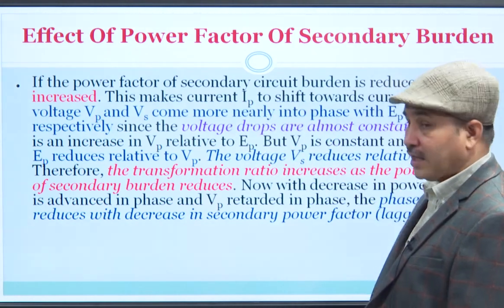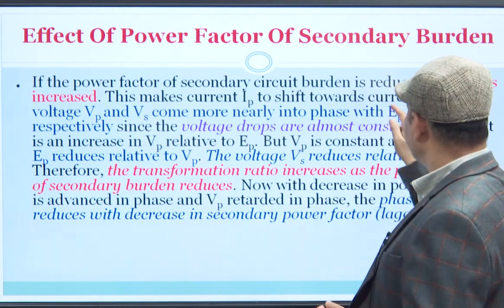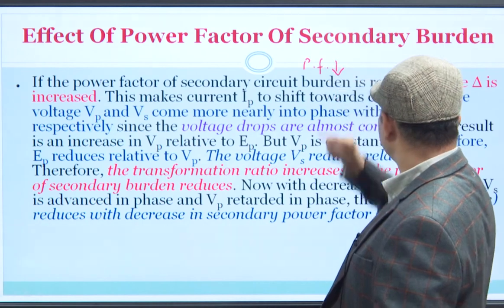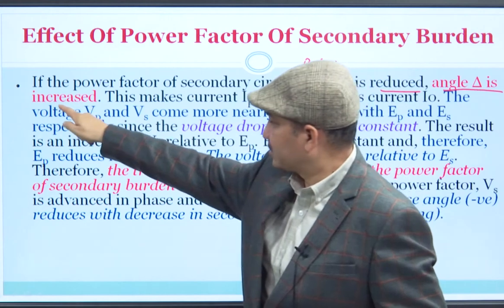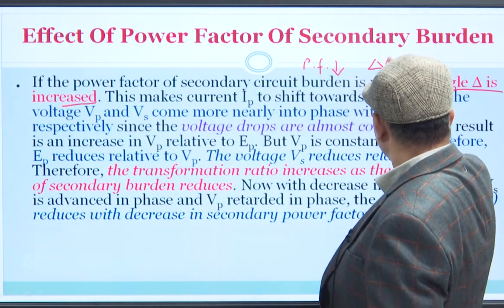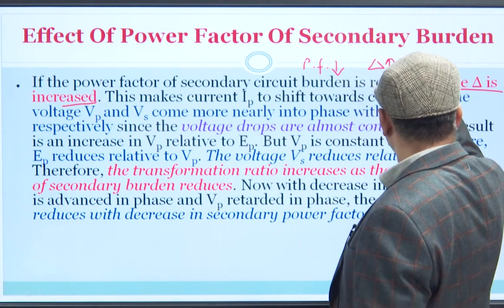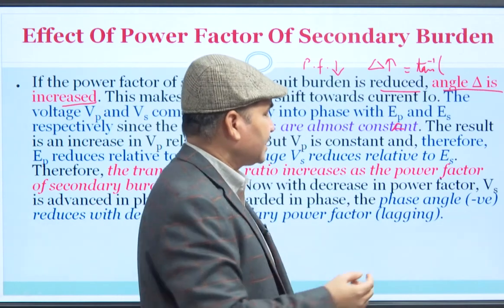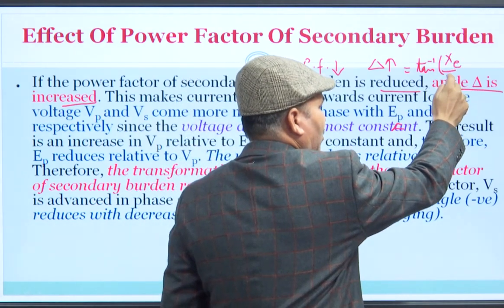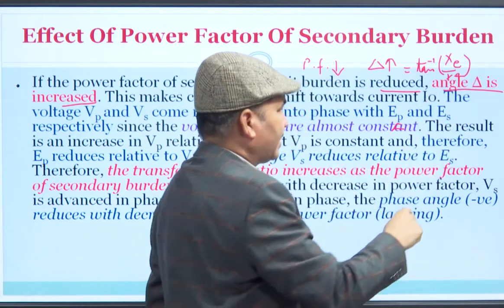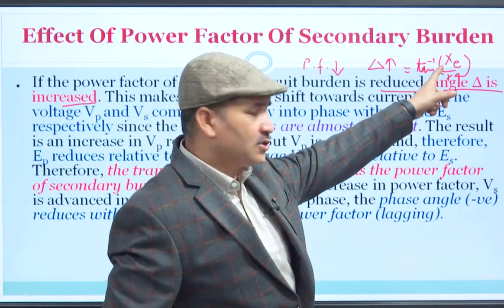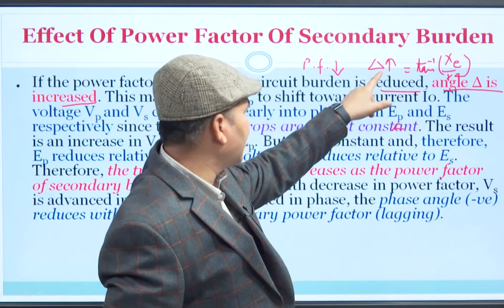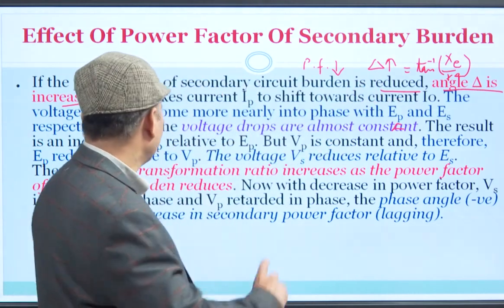Now, the effect of the power factor of secondary burden: if the power factor of the secondary circuit burden is reduced, the angle delta is increased. Delta is basically tan⁻¹(Xe/Re), where Xe is the reactance of the external burden circuit and Re is the resistance of the external burden circuit. So if we reduce the power factor, that angle delta increases.